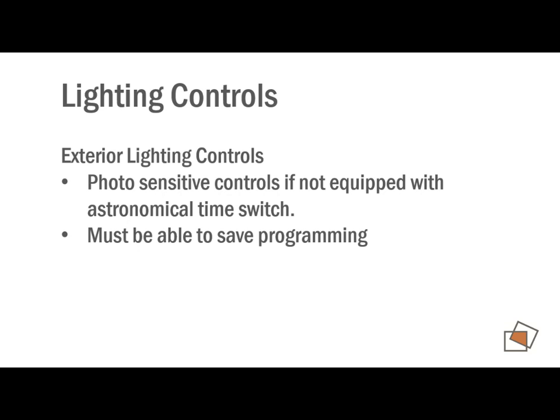Exterior lighting controls need to be photosensitive or controlled with an astronomical time switch. So this is just saying if you're turning your lights on at night, you can't just have a dumb time switch that doesn't know the changing of the sun. It needs to be astronomical, so it adjusts that on-off cycle with the changes from dawn to dusk. Or you can control it with a photocell. And then the code says if you lose power, it has to be equipped with memory that'll save your scheduling when power goes out. In future versions of the code, you get into some of the dimming requirements that you'll see more of, where parking lot lights maybe have to dim if they don't sense anybody there. But those are coming more in the 2015, 2018 code cycle, so not totally in play in 2012.